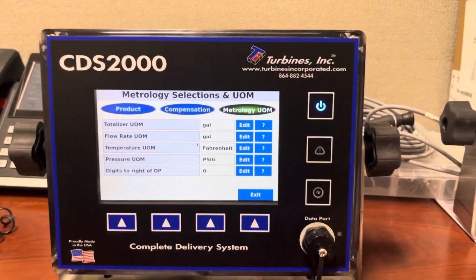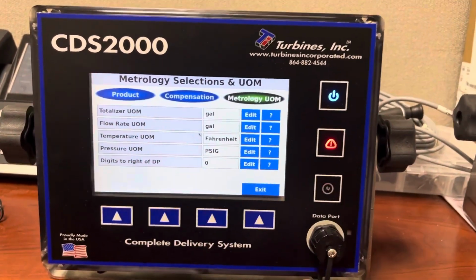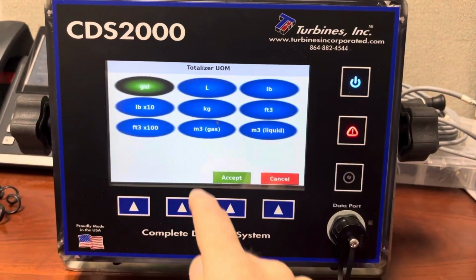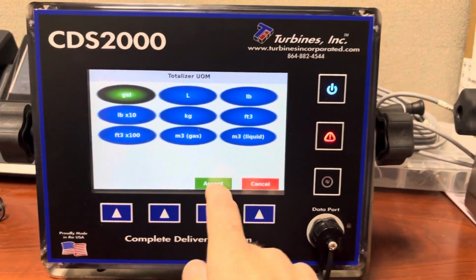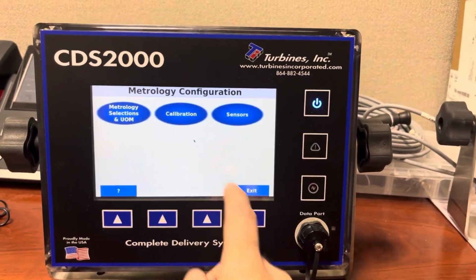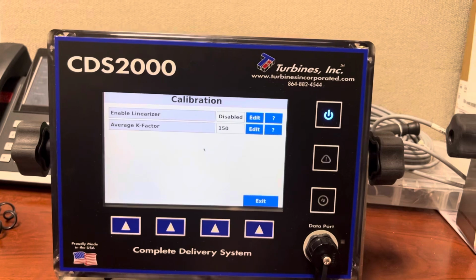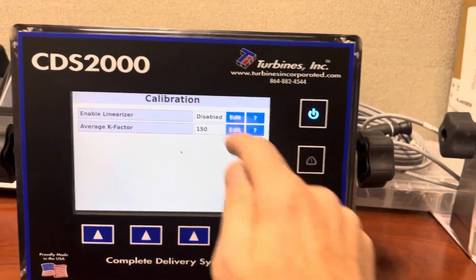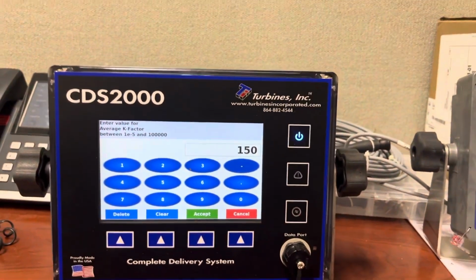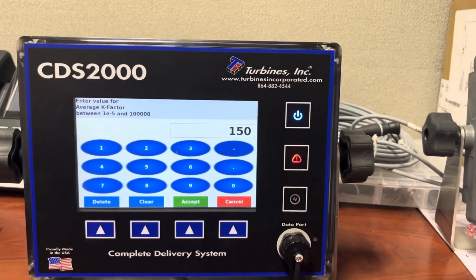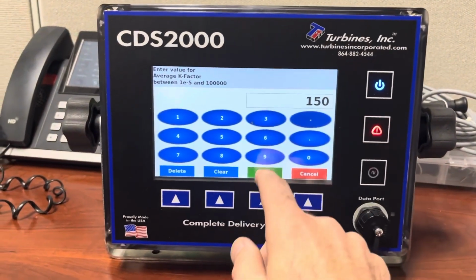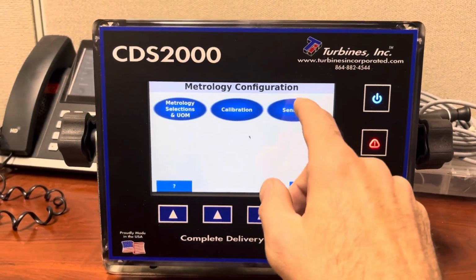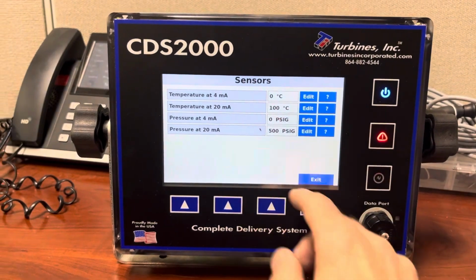And then metrology units of measure. This is where you can change from either gallons to standard cubic feet, pounds, or you name it, okay? So you'll exit out. The next one, calibration. This is where you are going to change your K factor. So whenever you have a new meter or you calibrate your unit, this is where you're going to change your K factor. And then finally, sensors, you won't need to go there. This is all for internal setup.